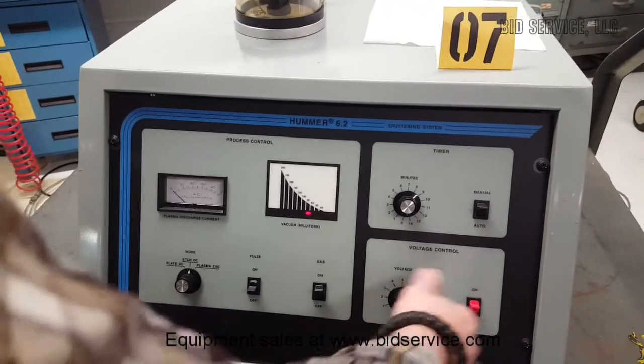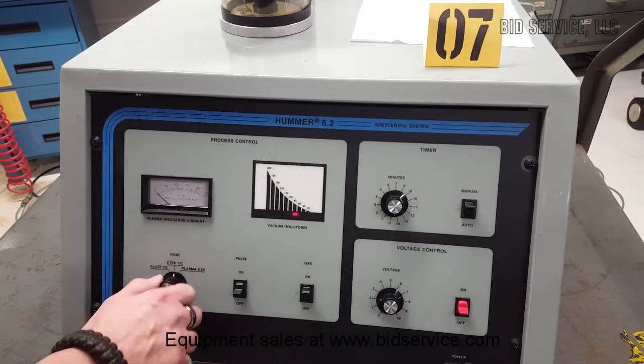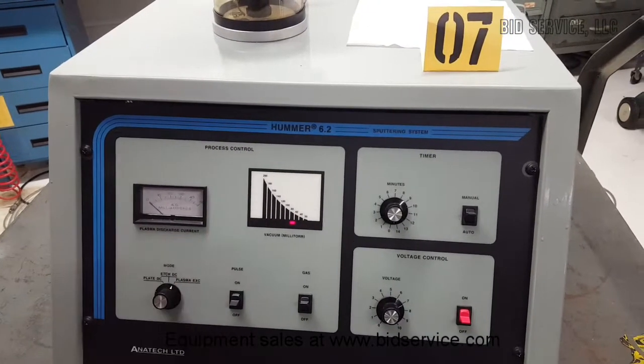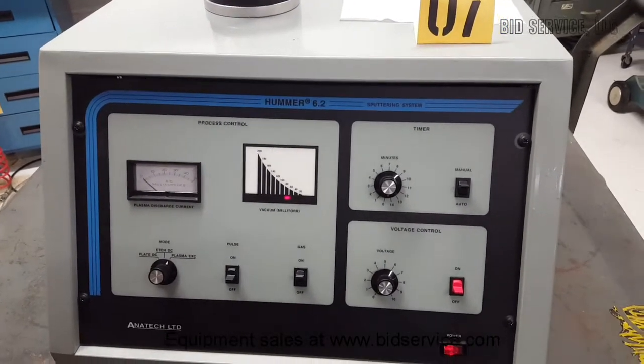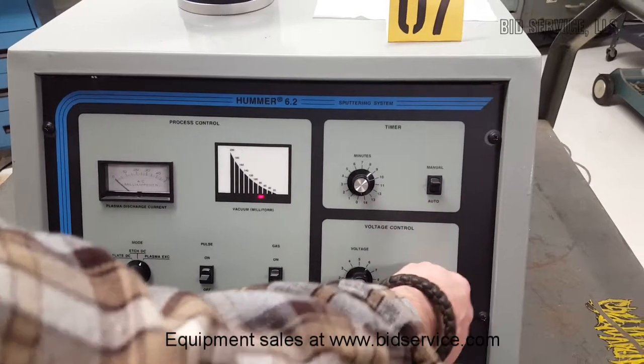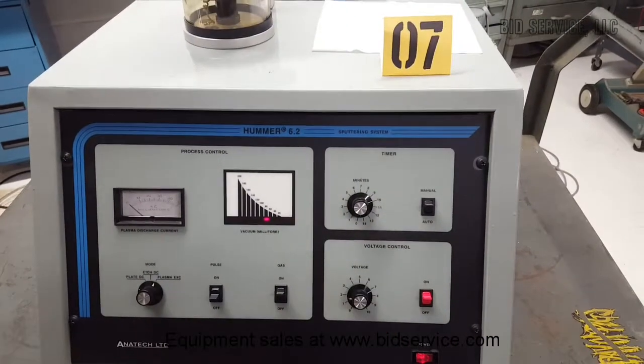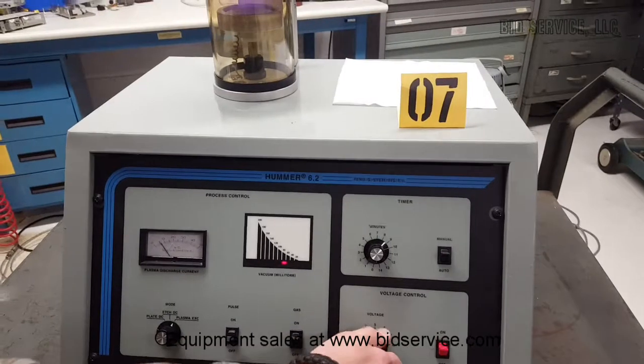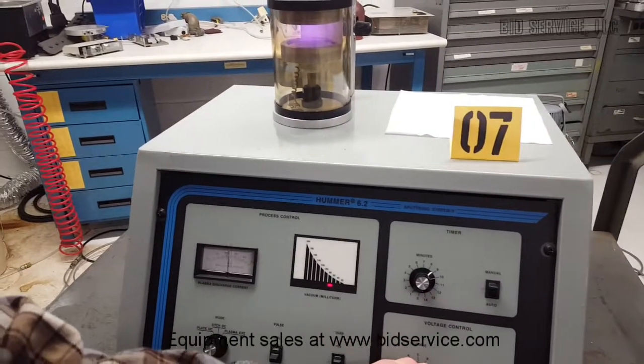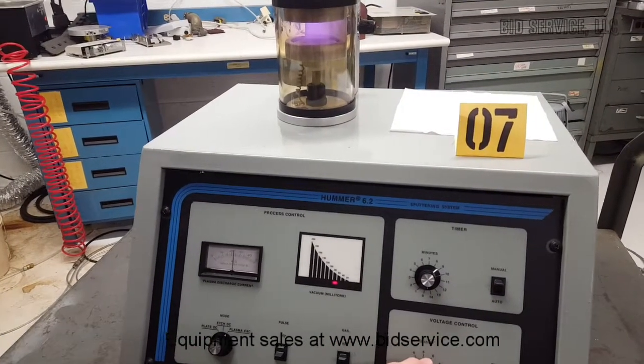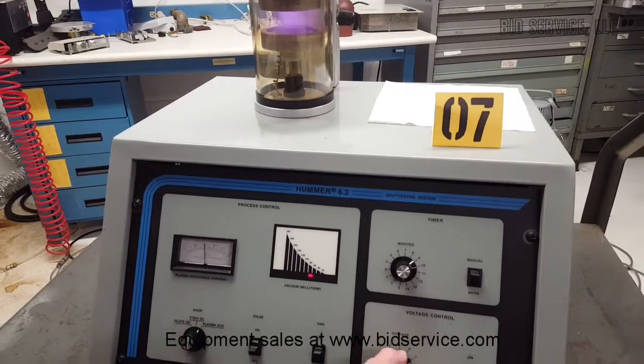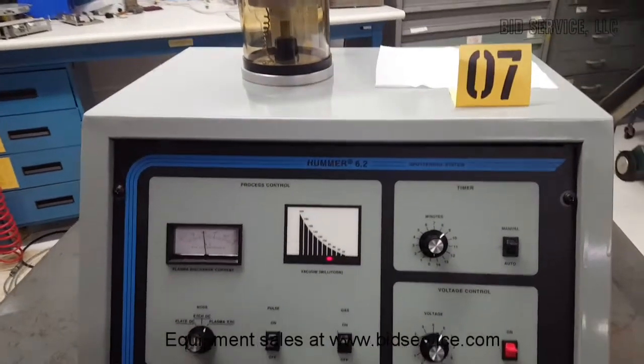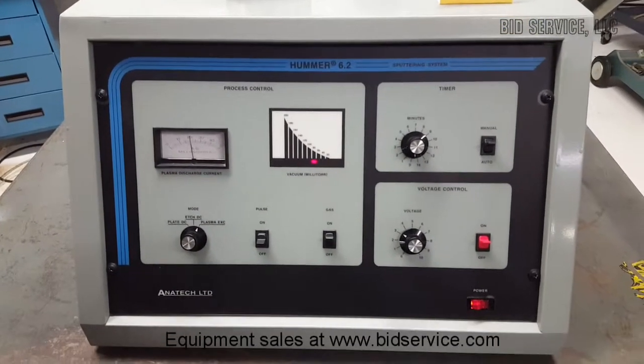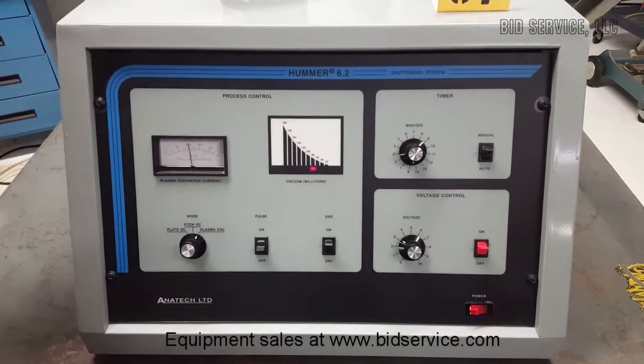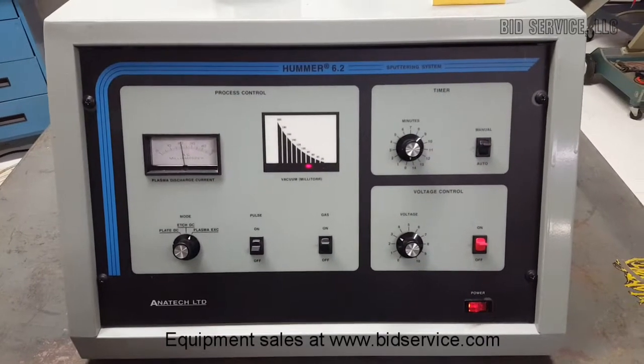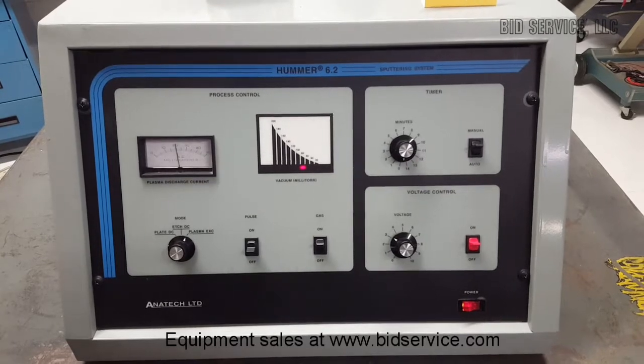Then the last stage is plasma etching. That's actually an alternating current voltage, which basically does a microscopic level scrubbing of your sample. And that one is also a 20 milliamp limit, recommended by the manufacturer. The argon gas that you would connect to the supply, they recommend no more than 5 to 6 psi.